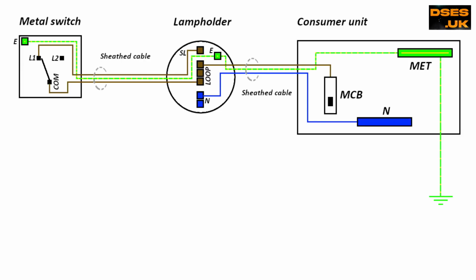Here's a graphical representation of what this might look like. Not quite what James was seeing, as I'm only using one lamp, but again, it all boils down to the same shit. Switch 1, the metal switch, has here a good circuit protective conductor. If wired in twin and earth, that earthing conductor to the switch runs between two other cores, a permanently energised line and an occasionally energised switch line, and it has continuity throughout from the exposed metal of the switch plate all the way back to the supplier's earth, back at the source of the installation.